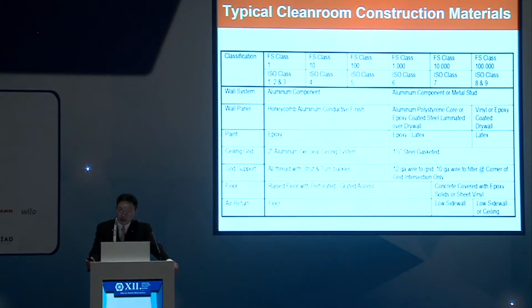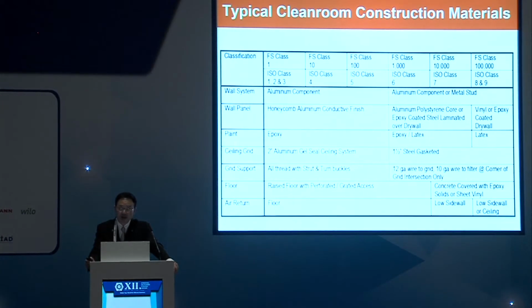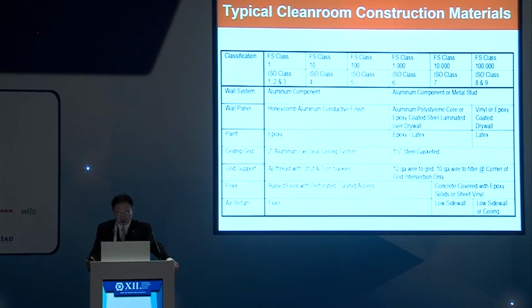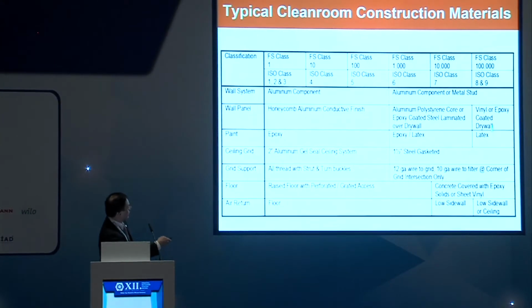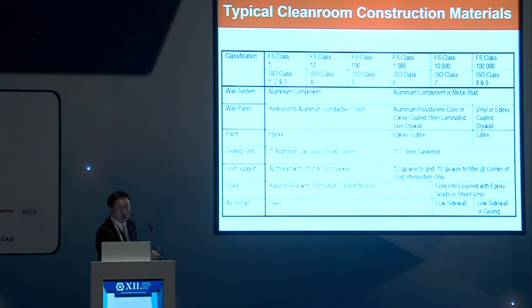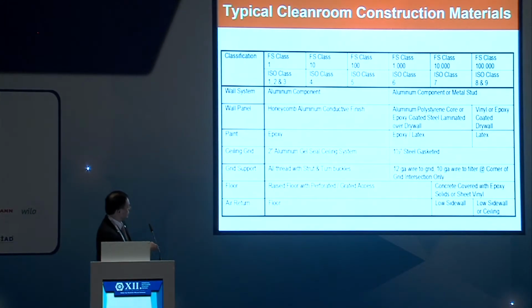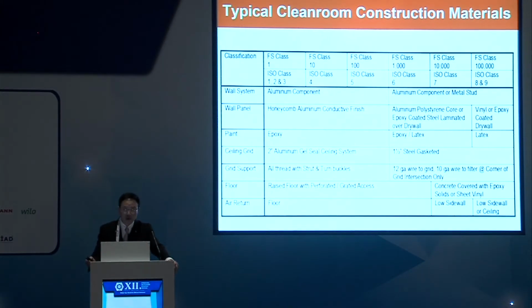And also the T-bar ceiling is different. For the cleaner class, because you put in so many fan filter units, it is much heavier, and you also have a seal leakage issue. So sometimes use a 1.5 inch, sometimes use a 2-inch T-bar ceiling. And also the floor treatment could be different. For the cleaner class, typically use a raised floor. And for a less clean class, you can use the low sidewall return. So that's the few key differences between the commercial space design and the clean room space design.